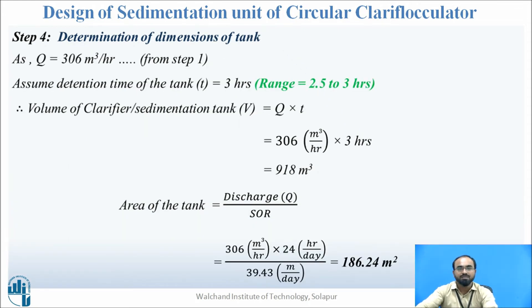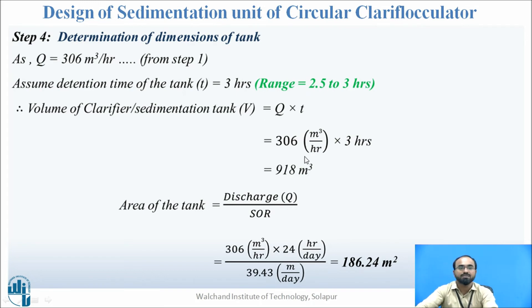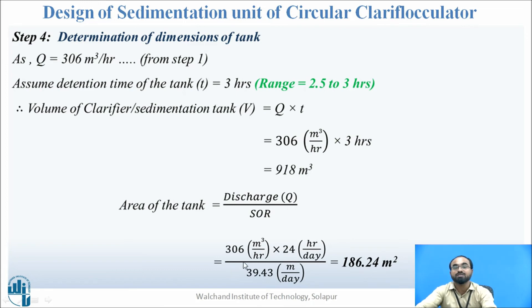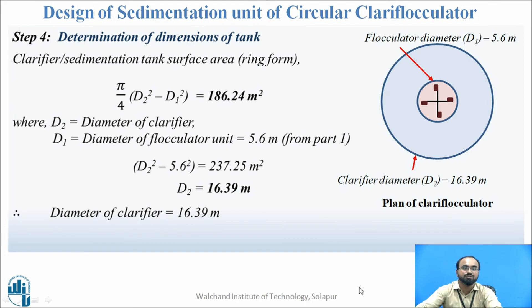Now we calculate dimensions. Q = 306 m³/hr, detention time assumed as 3 hours. Volume = Q × t = 306 × 3 = 918 m³. Area = Q / SOR = (306 × 24) / 39.43 = 186.24 m². Since this is the total area of the clarifier ring, we subtract the flocculator area.